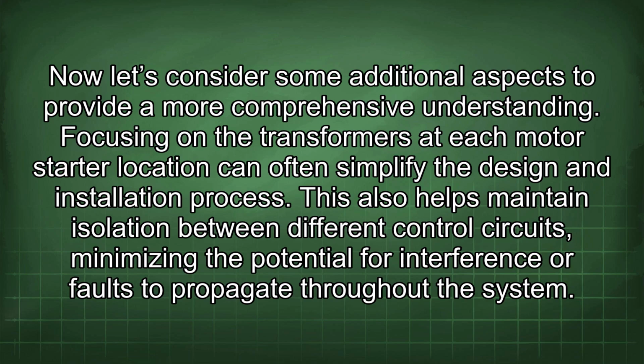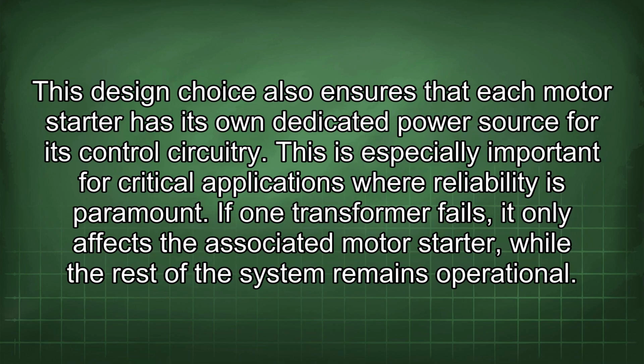Now let's consider some additional aspects to provide a more comprehensive understanding. Focusing on the transformers at each motor starter location can often simplify the design and installation process. This also helps maintain isolation between different control circuits, minimizing the potential for interference or faults to propagate throughout the system. This design choice also ensures that each motor starter has its own dedicated power source for its control circuitry. This is especially important for critical applications where reliability is paramount. If one transformer fails, it only affects the associated motor starter, while the rest of the system remains operational.